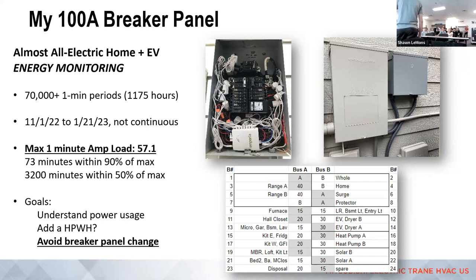Over 70,000 minutes of data over this winter, 70,000 one-minute segments of data. What I found out is that my absolute worst case one-minute data was 57 amps. That's with electric dryer, EV, all electric appliances, heat pump, all that stuff. I have an all electric house effectively with an EV, and the max amperage on my 100 amp panel is nowhere near my 100 amp limit.